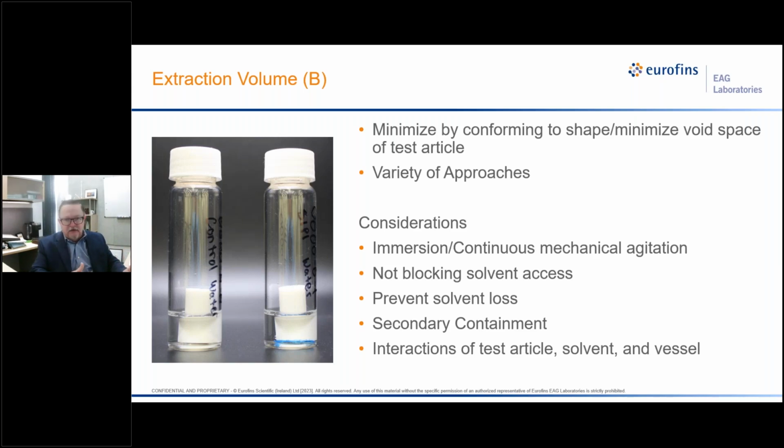Now, there are a lot of things you need to consider when doing this. I kind of touched on some of those, but the big one is really making sure that that device is fully immersed in the extraction solvent. And I think sometimes that can be challenging, especially if you have odd-shaped devices or very linear devices, and you need to come up with creative ways to ensure that those devices remain in solvent contact for the entire extraction time. The picture on the left there is a suture or a thread that was floating on top of the extraction solvent. So you may also have to find ways to actually fully immerse it, hold it underneath the extraction solvent, which is the case here.